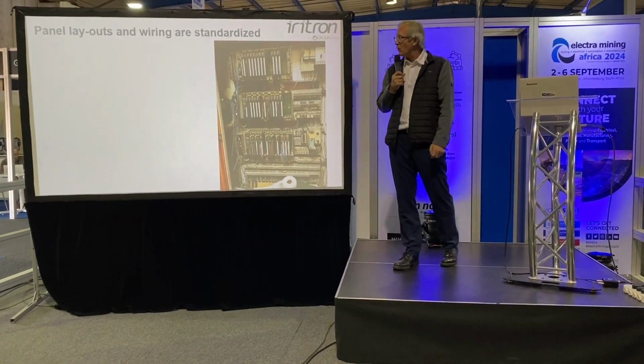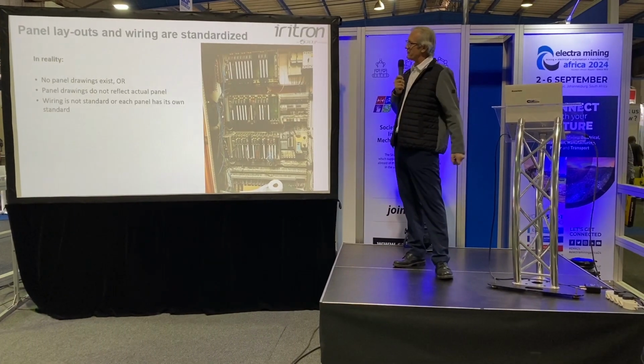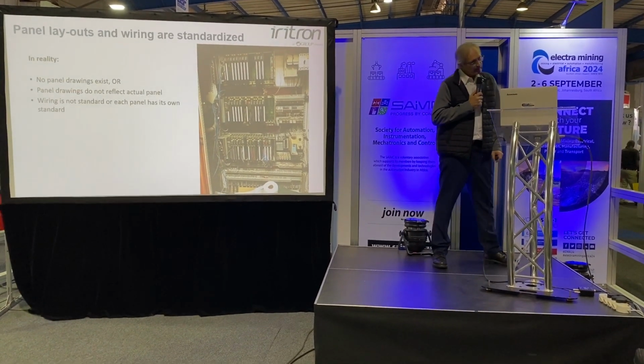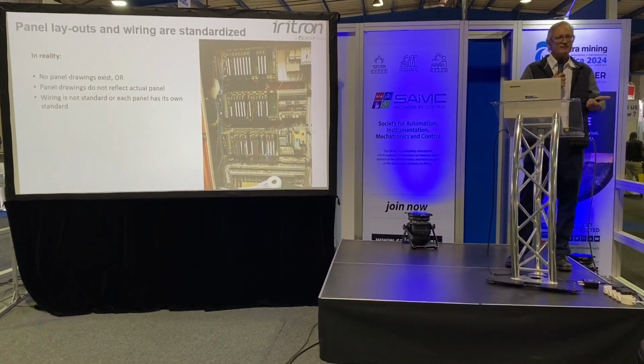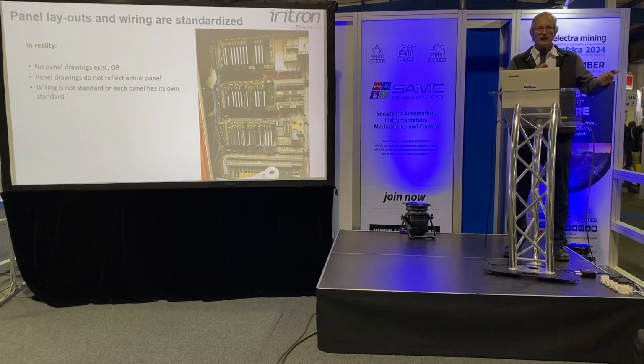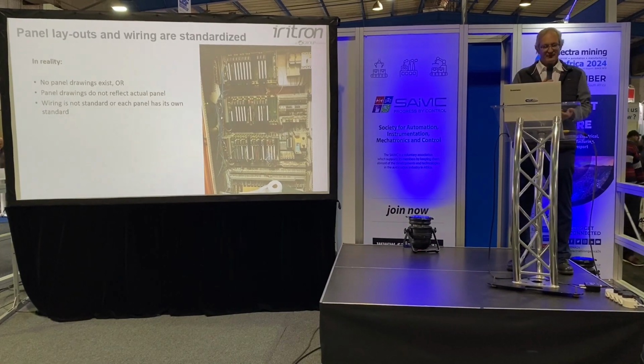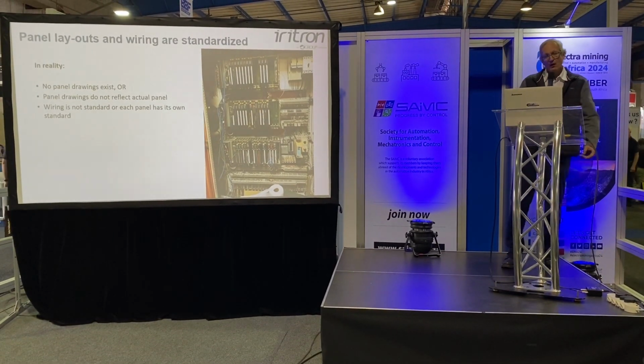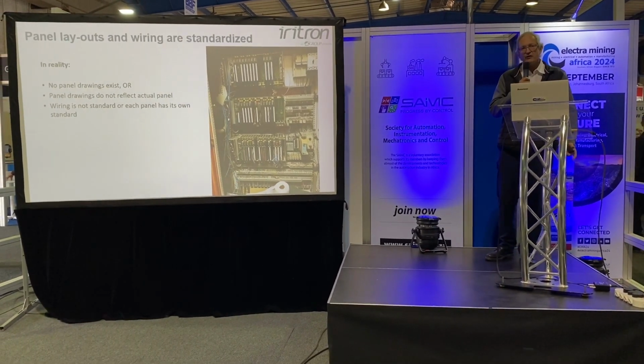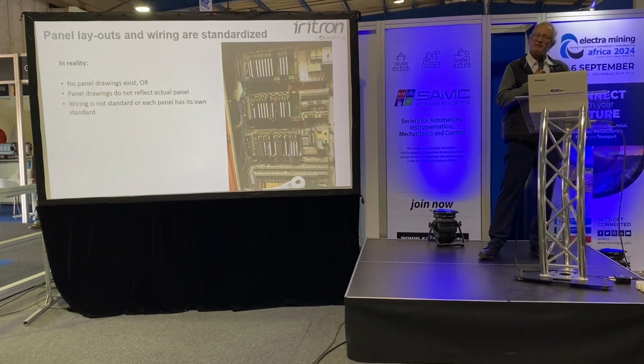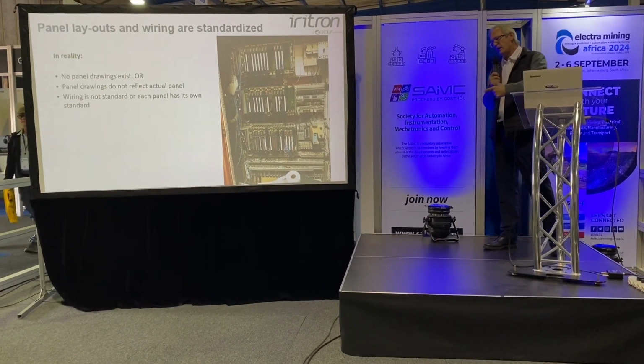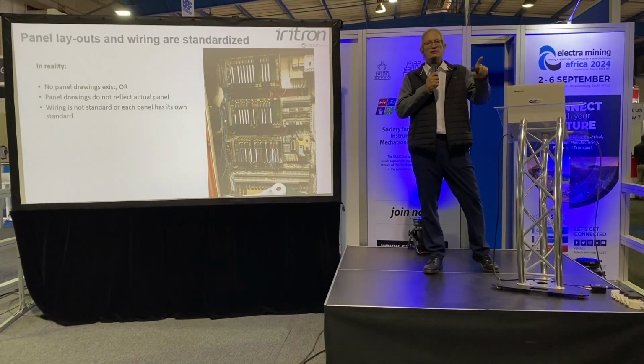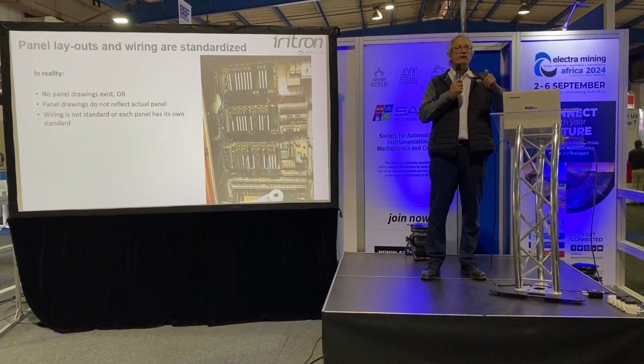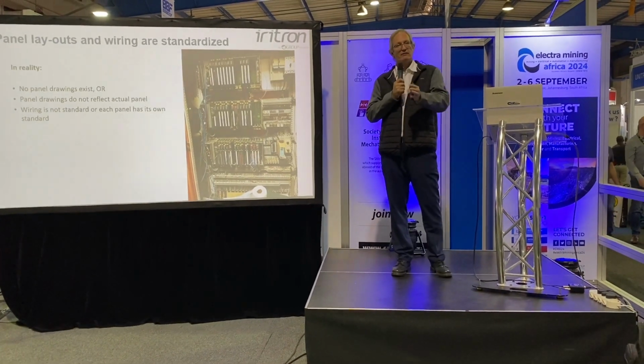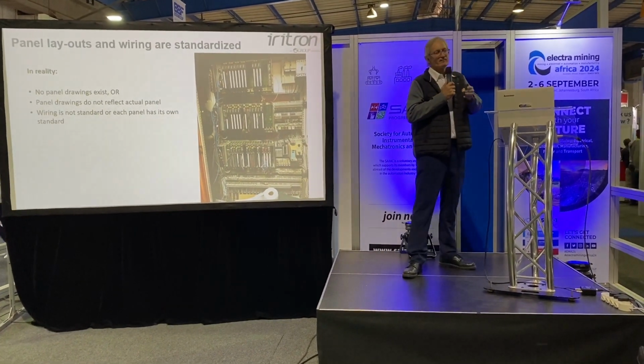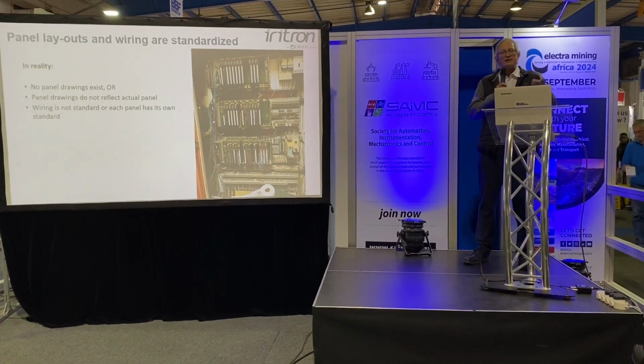Then, panel layouts and wiring are standardized. That's also a big myth that we find, because in reality, it's not standardized. There are no panel drawings, because the panel drawings got lost 5 years ago, 10 years ago, when we moved our offices, or when we went into new offices. Or we do have the panel drawings, but they're outdated by 5 to 7 years. We've never updated them. Or we find in the panels that there are some standards, but the standards are not consistent. Each panel has its own standard from before the company decided to standardize everything. But everything before that point is not standard. And using different subcontractors, that standard wasn't applied throughout.